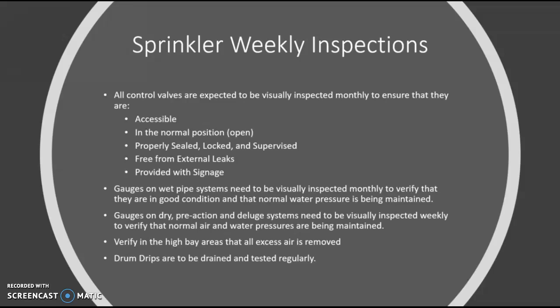Now, for this facility, we have all control valves expected to be visually inspected and ensure that they are accessible in the normal open position, properly sealed, locked, and supervised, free from any external leaks, provided with signage. All of these are NFPA 25 guidelines.